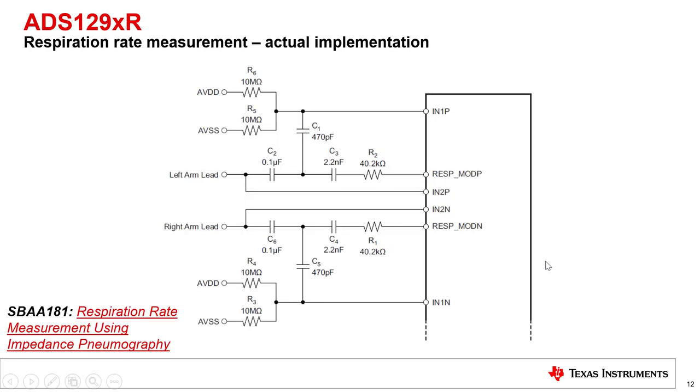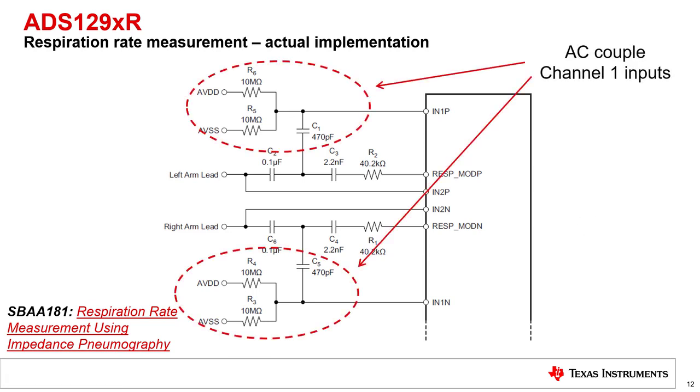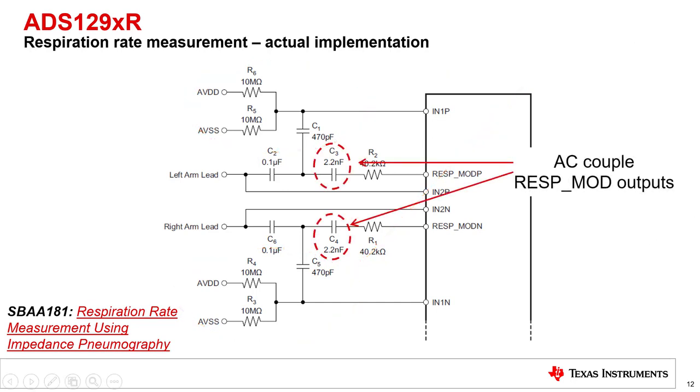The ADS129XR actually implements this using several passive components. Capacitors C1 and C5 in this diagram are used to AC-couple the electrode inputs. Resistors R3, R4, R5, and R6 form resistor dividers on each input to bias them back to mid-supply. C3 and C4 are used to AC-couple the respiration modulation signal on the RESP-MODP and the RESP-MODN pins. Series resistors are also used to limit the AC current.